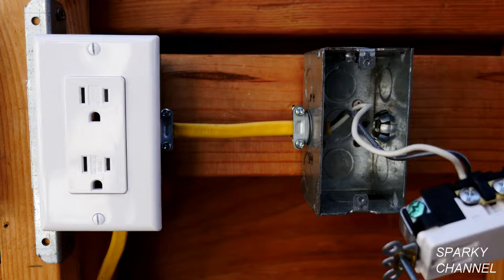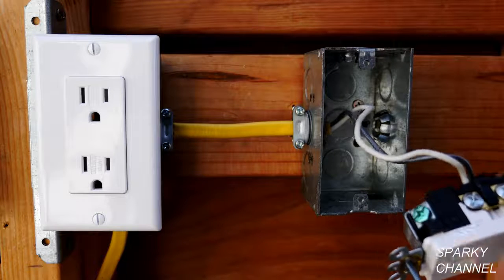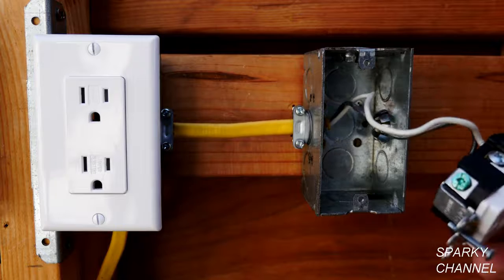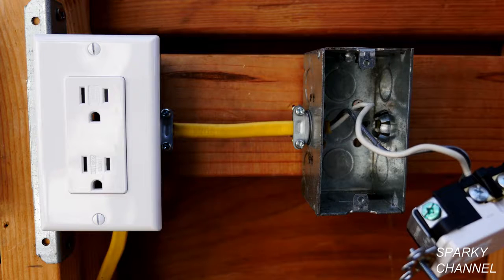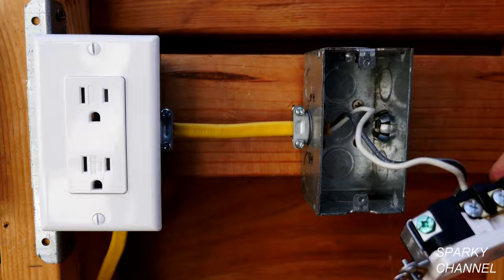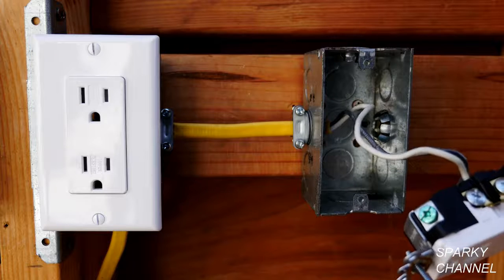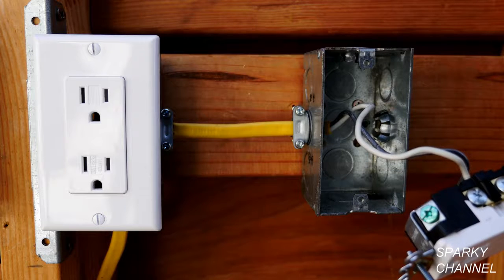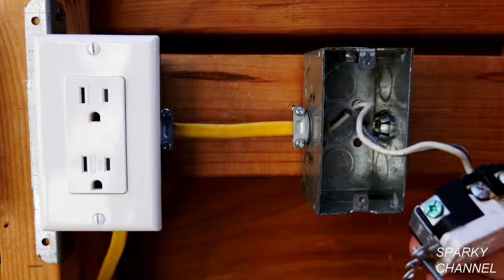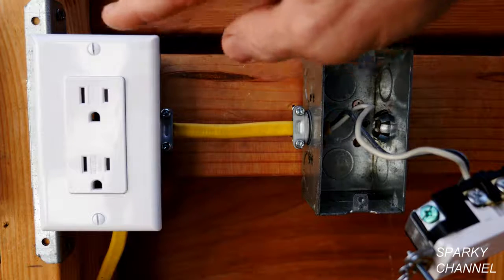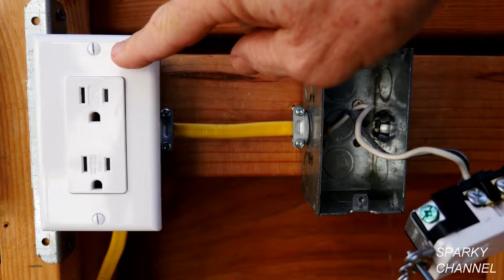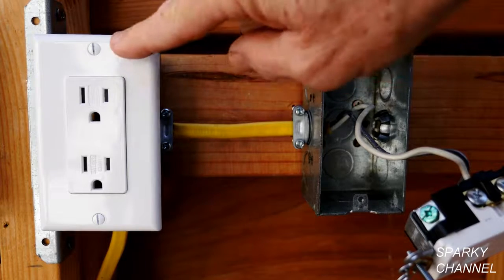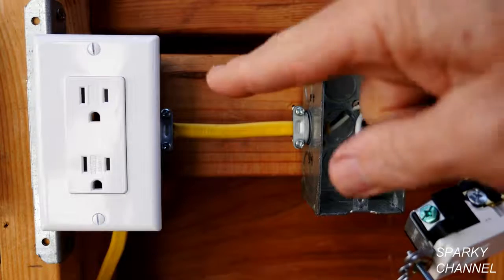If you see a broken ground wire or a ground wire that is not hooked up to the green grounding terminal, then that's an easy fix. You just hook the ground wire to the green grounding terminal. But this is a situation where there's no ground wire in the box. However, this box right here tested as correct wiring. So we know there's a ground in here, a proper ground.